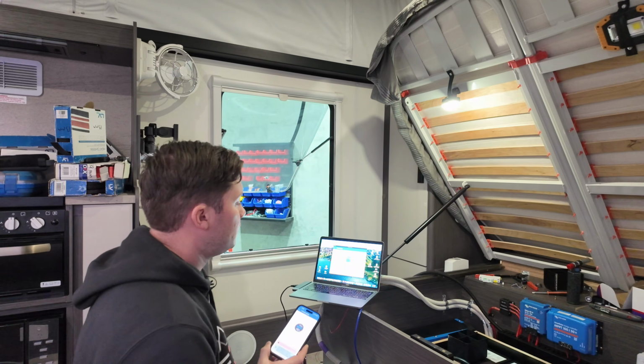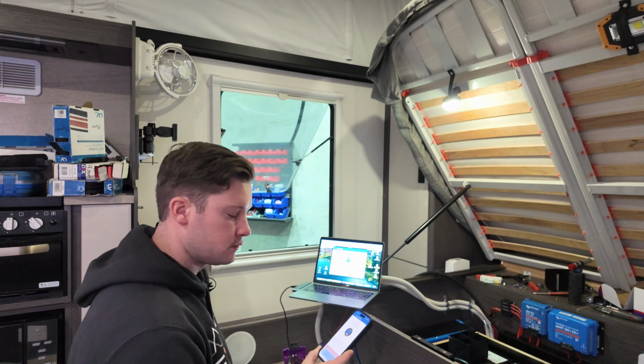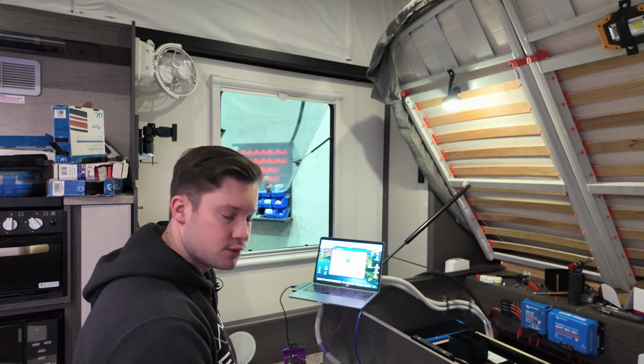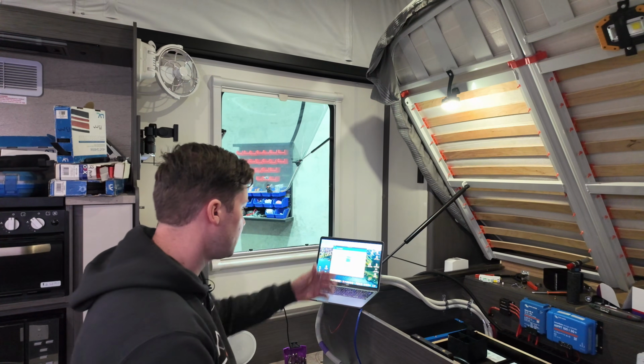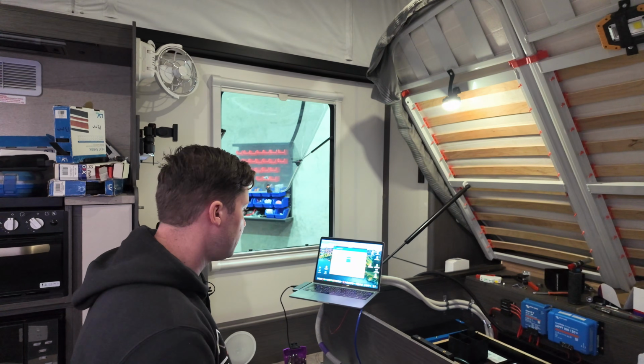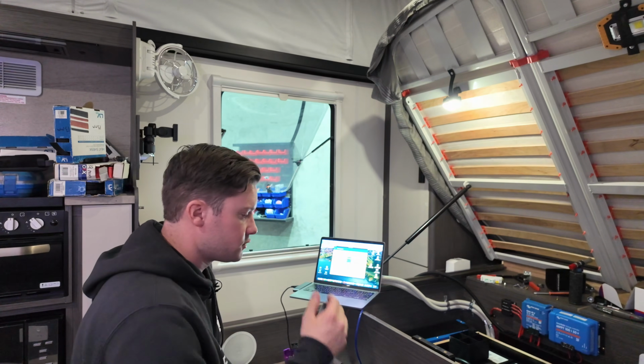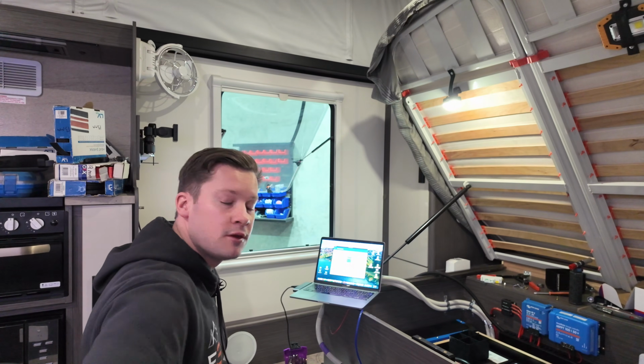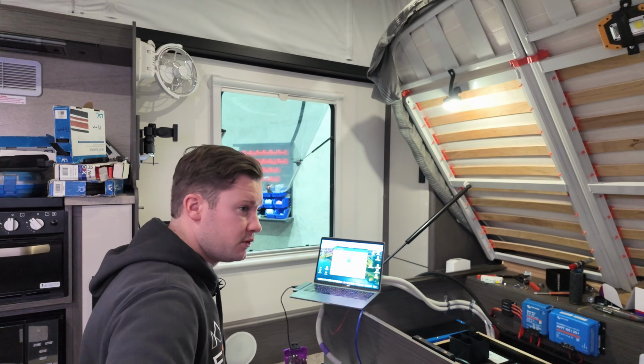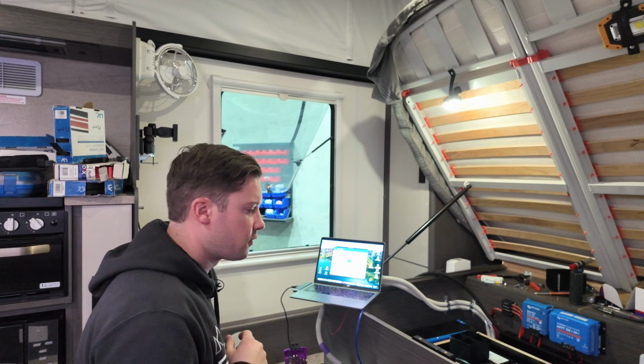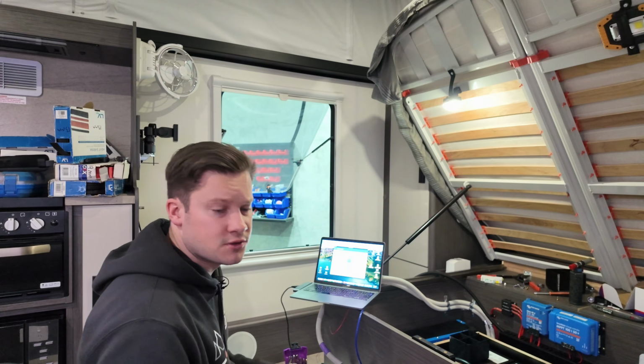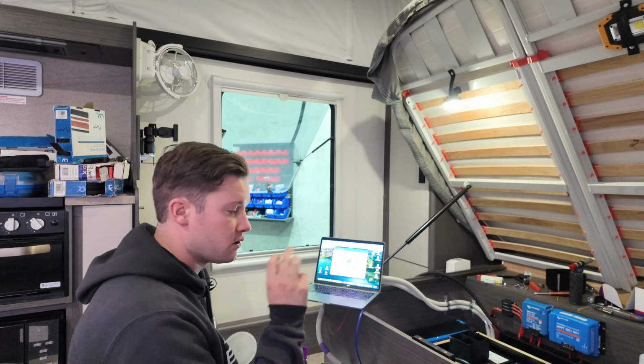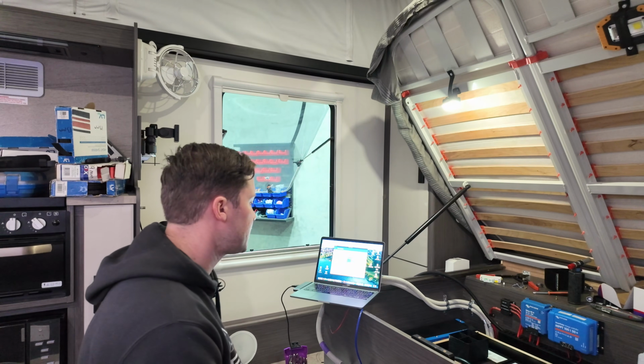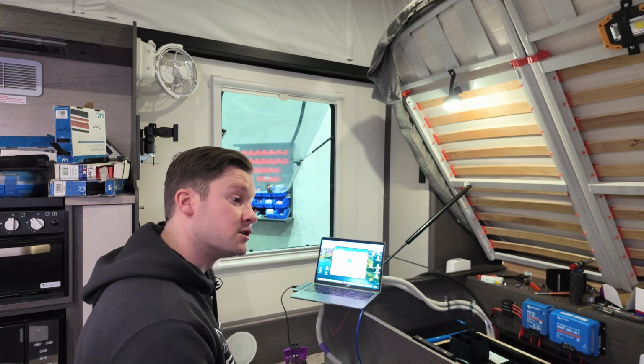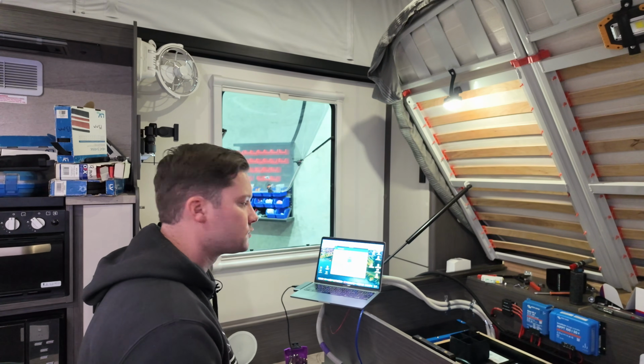Another piece of the puzzle is doing all the software updates across all the charging devices. They just come with a sort of stock firmware. For the multi-plus, for example, we're updating from 508 to 522, making sure that a lot of the stock lithium settings, which will be 14.2 for an absorption charger, we change to 14.4, and our float charge from 13.5 to 13.6, because we know that's what these batteries and the BMS inside them need to charge to the full 100%. That's one big thing.